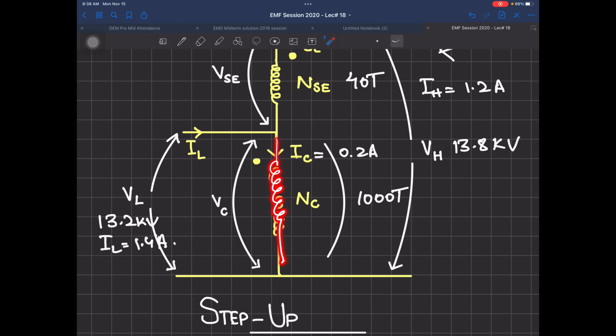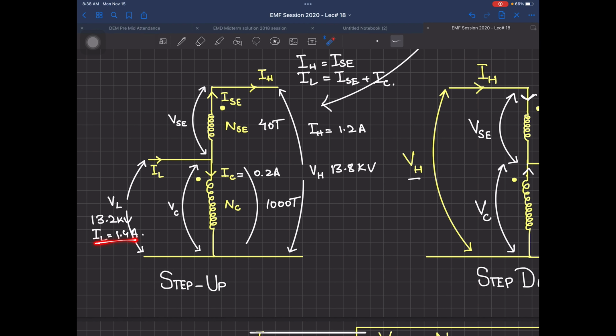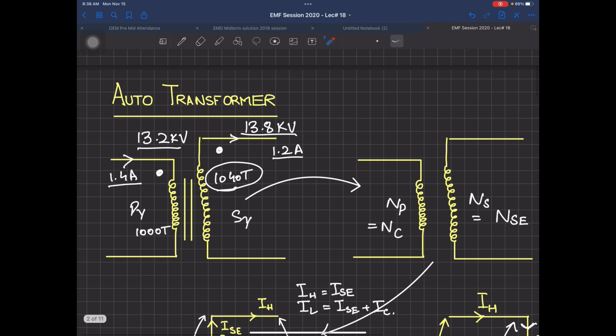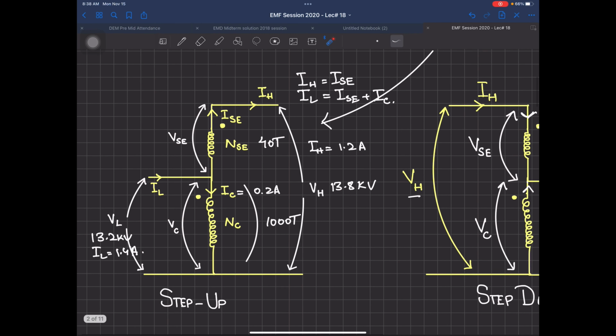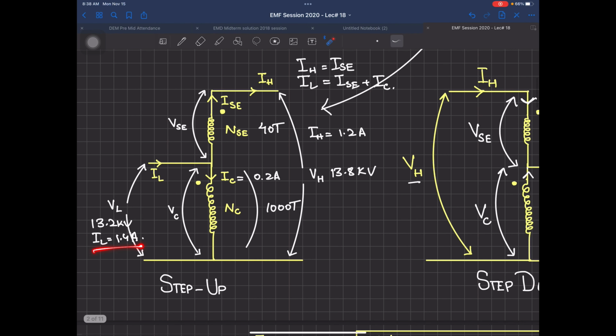I'm repeating this, listen carefully. You had 1.4 ampere on the low voltage side, 1.2 ampere on the high voltage side current - I have taken these values from before, you can do the mathematics yourself. Now if 1.4 ampere is the low current which goes here, and high current is 1.2 ampere, certainly out of this 1.4, 1.2 is going over here. The remaining 0.2 will flow here, according to KCL. This 0.2 means this winding does not have to withstand 1.2 ampere - it only has to handle 0.2 ampere, so your cost is significantly reduced.